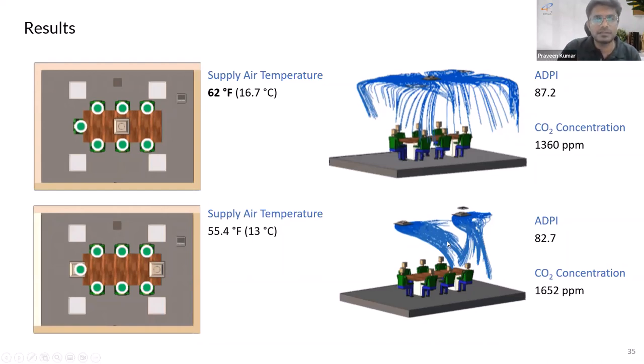That needed to run at maximum capacity, like 55 Fahrenheit, to achieve the same level of comfort as the design configuration. When I compare the ADPIs, it's slightly lower for the second configuration, maybe because of the size of the diffusers, and the CO2 concentrations are also higher compared to the design one.